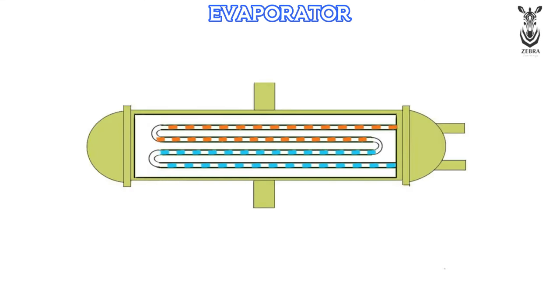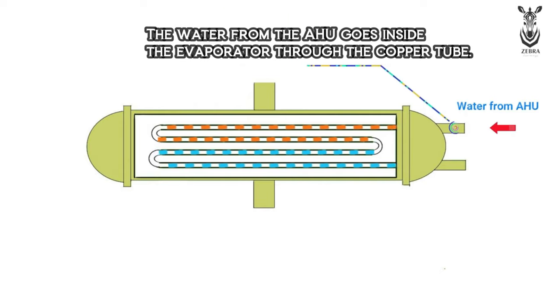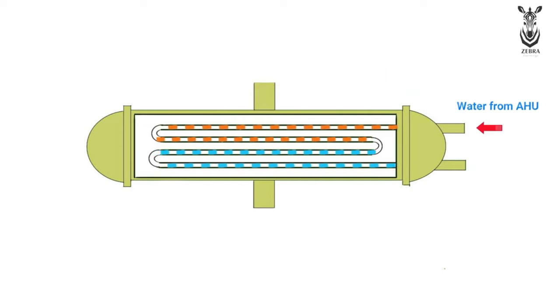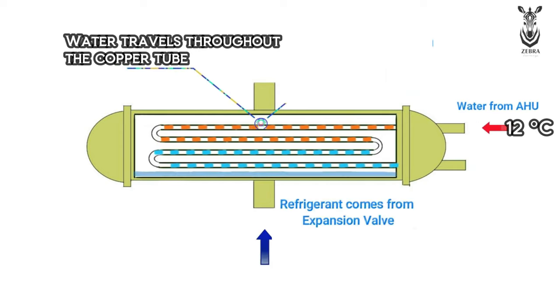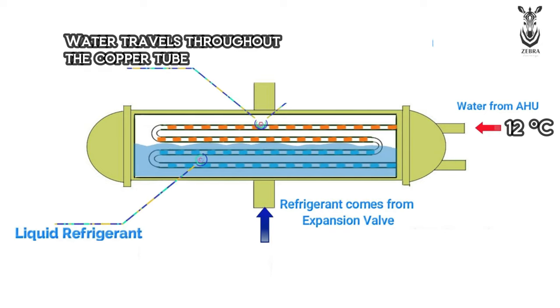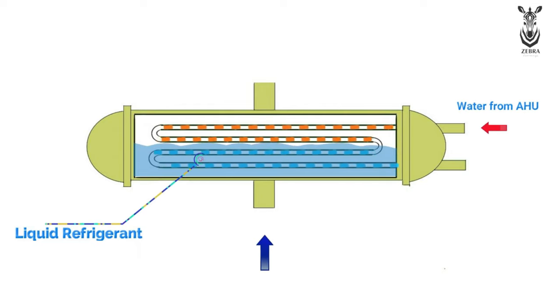Next, the refrigerant will enter into the evaporator. The evaporator is also similar to the condenser. In the condenser, the water from the cooling tower enters through the coil, but in the evaporator, the water from the AHU enters through the coil. The water from the AHU will enter into the evaporator at 12 degrees Celsius and will travel throughout the coil. The refrigerant that comes in cold from the expansion valve surrounds the coil inside the evaporator.